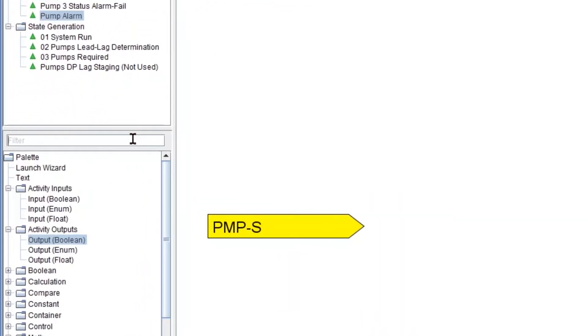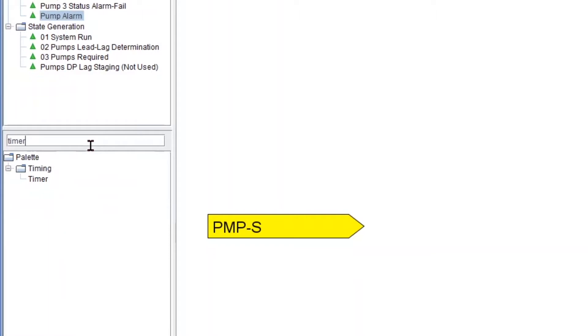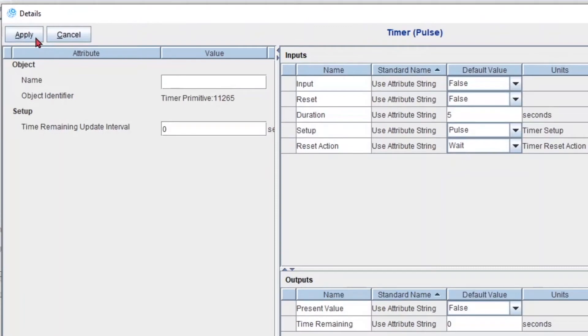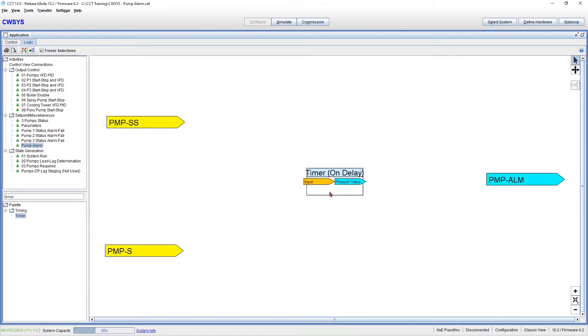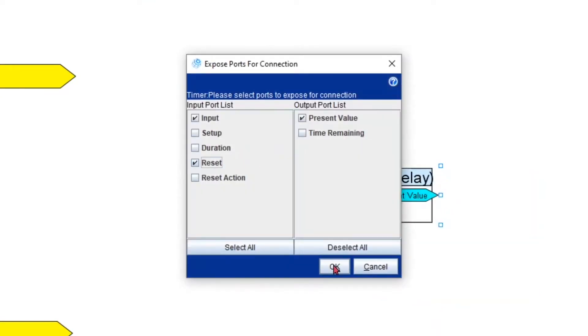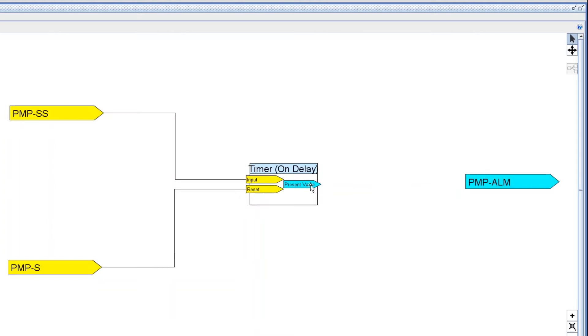Now let's add a timer — I'll just type 'timer' and drag it over. By default we get a timer set up as a pulse, so I'm gonna double-click to edit it and set this up as an on delay, which is key. I'm gonna make a 15-second delay — you can do 10 seconds. I'll apply and close. I also need another input on my timer, so I'll right-click, expose ports for connection, and add a reset. Then I'll connect my start-stop to the input, my status to the reset, and my output to pump alarm.